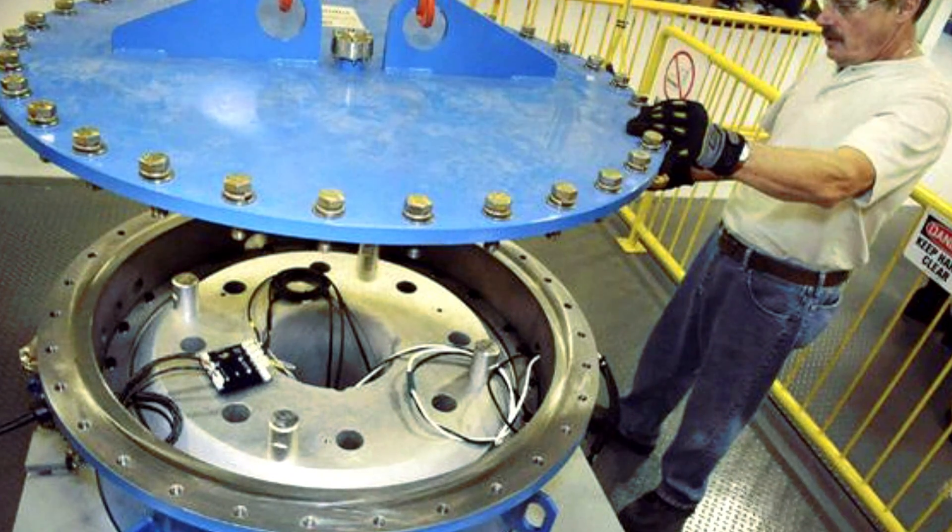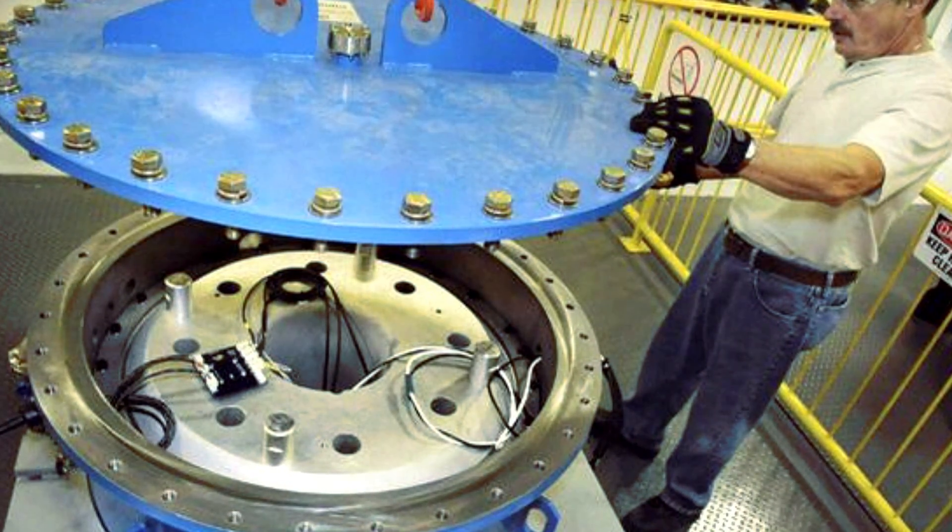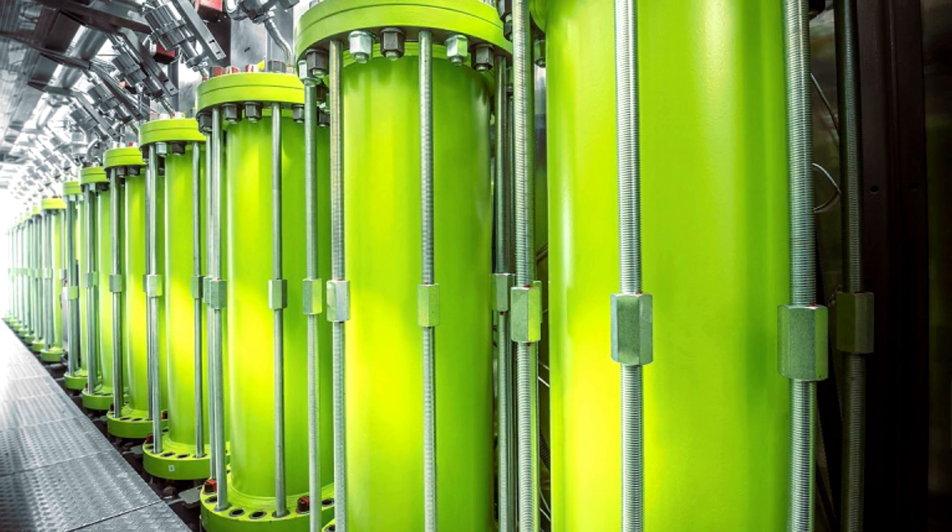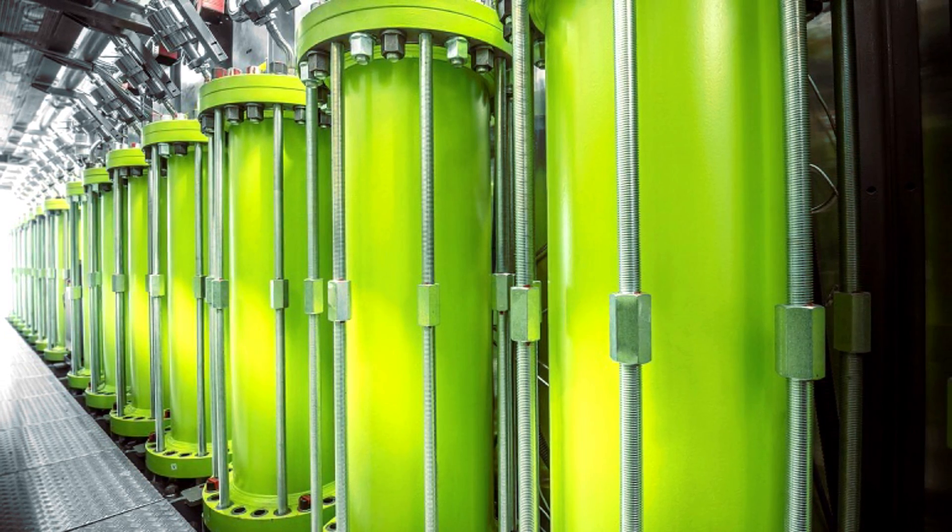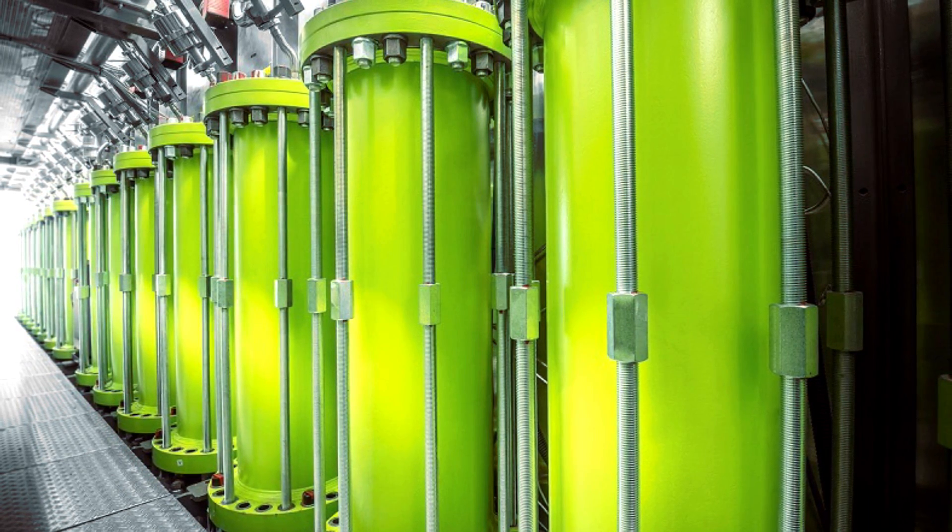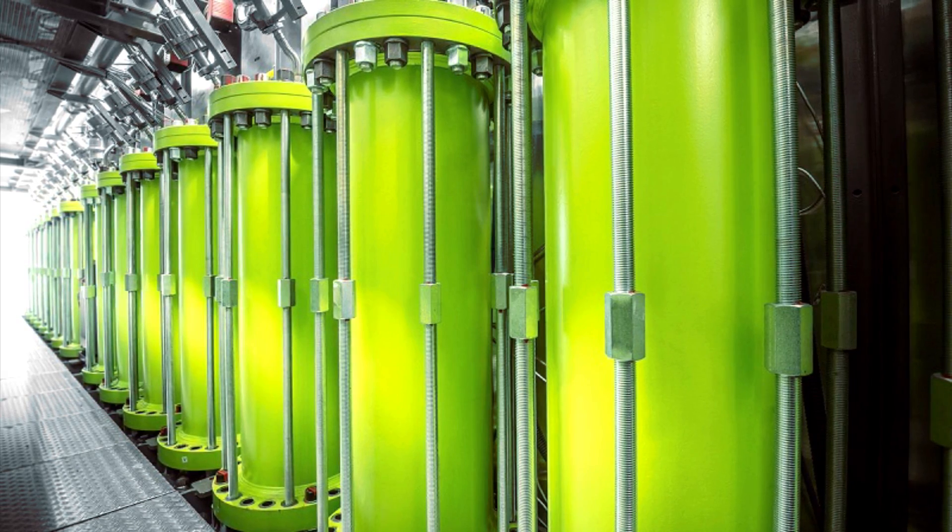Beyond the flywheel rotor, the housing of a flywheel storage system, though static, must be designed with containment in mind. They're generally designed to withstand the forces of the near-vacuum low pressures within the device as well as be able to contain the energy release of a catastrophic failure of the flywheel. Considerations for the heat generated by the motor generator must also be factored into the design.